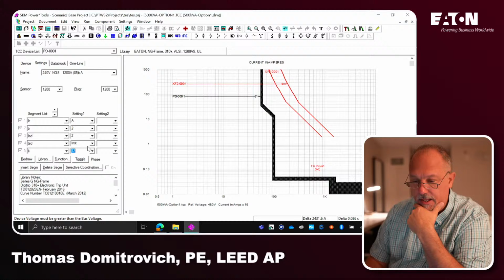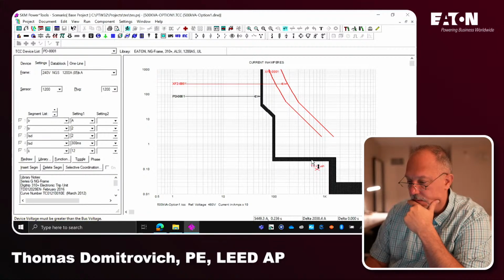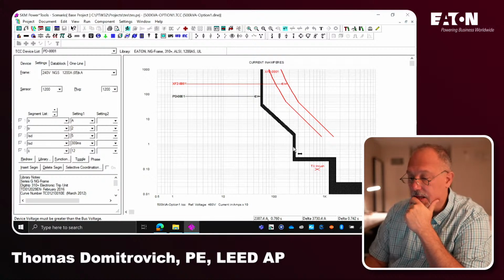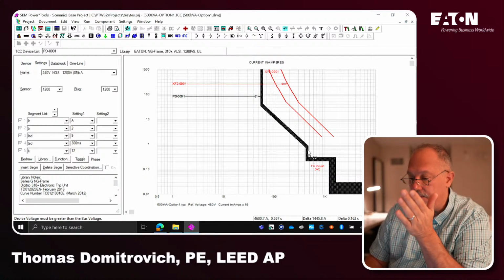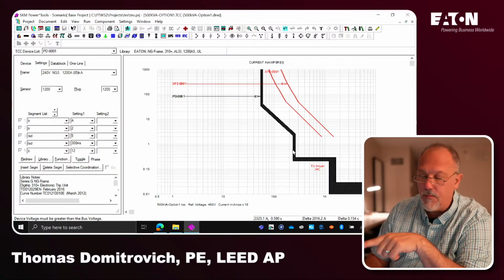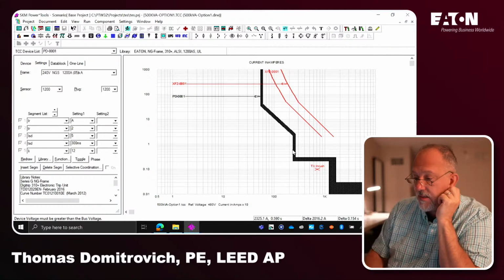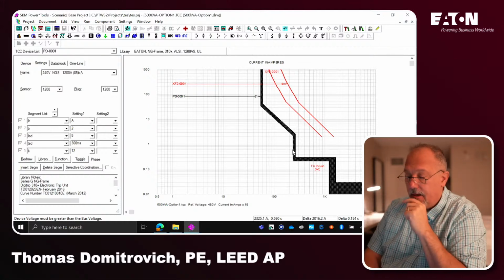Now I have to do the delay. Short time delay. I'm going to move this up. There it is. Whoa. Move it up. There we go. Now I'm riding through inrush. Riding on empty. All right. So then I can move this up this way to... when we run our arc flash study, we'll run it with... That may help incident energy on the primary. All right, so there we go.